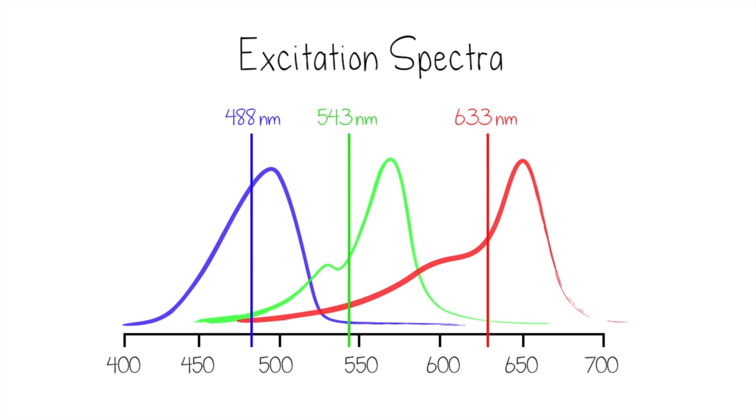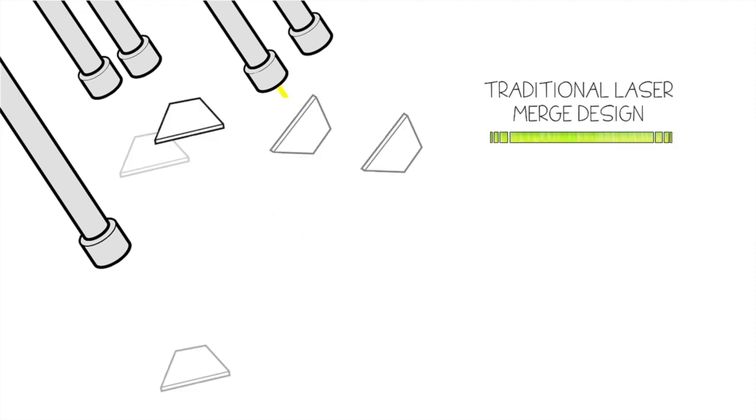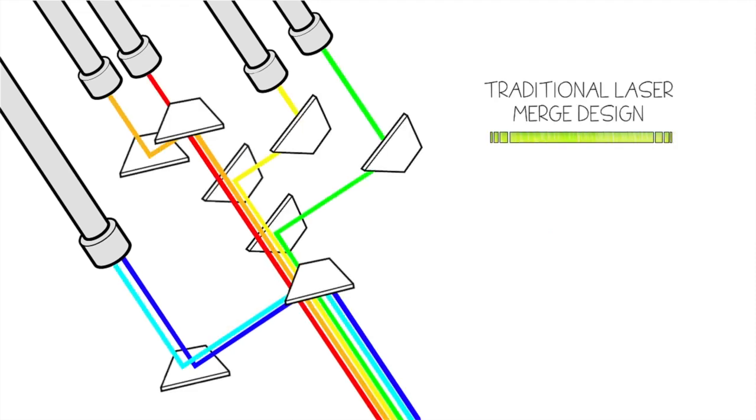To effectively excite the various fluorophores in a sample, multiple lasers are required. However, each laser adds bulk to the system, each laser generates heat, and each laser consumes energy. The individual lasers must be combined into a single imaging light path, which requires additional optics.